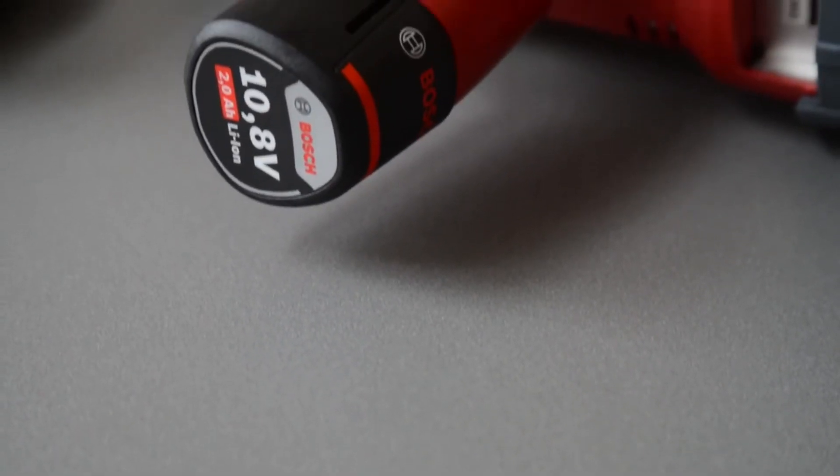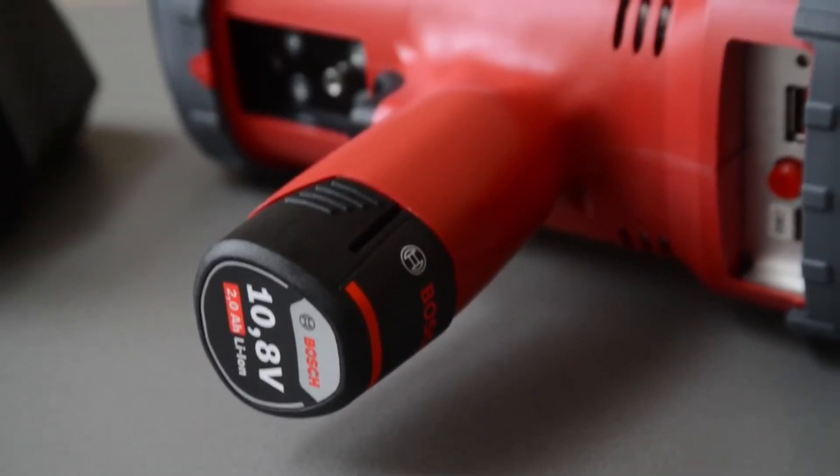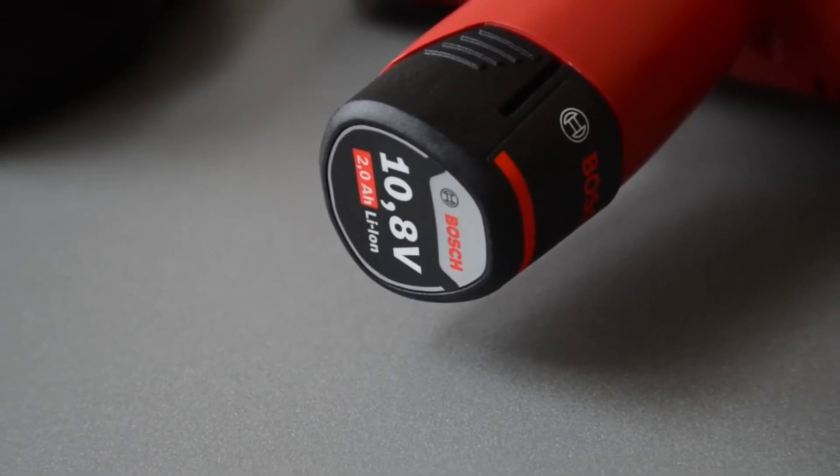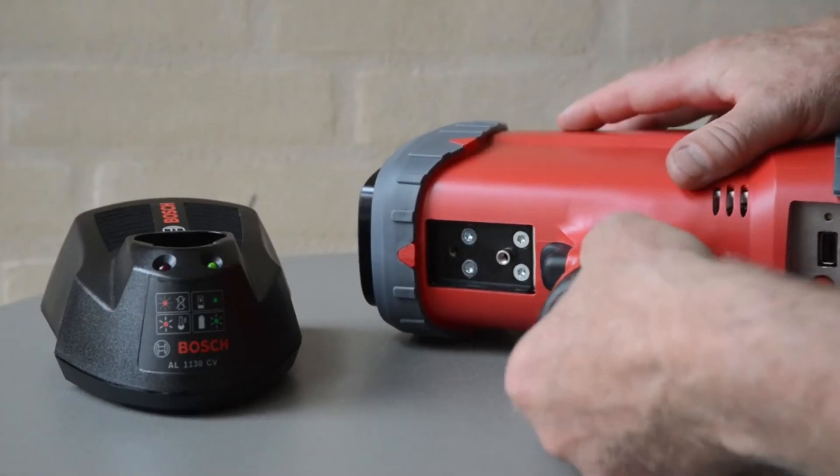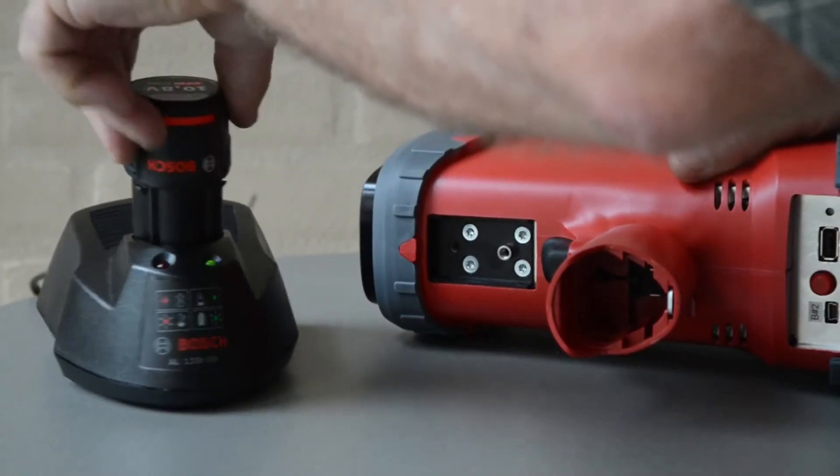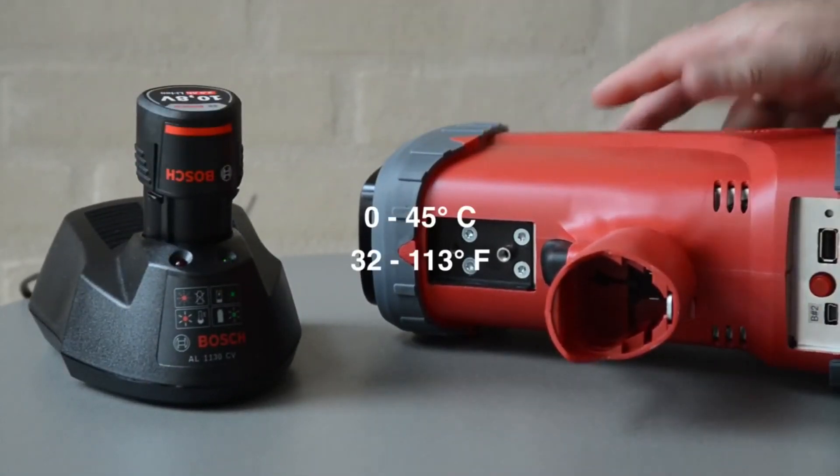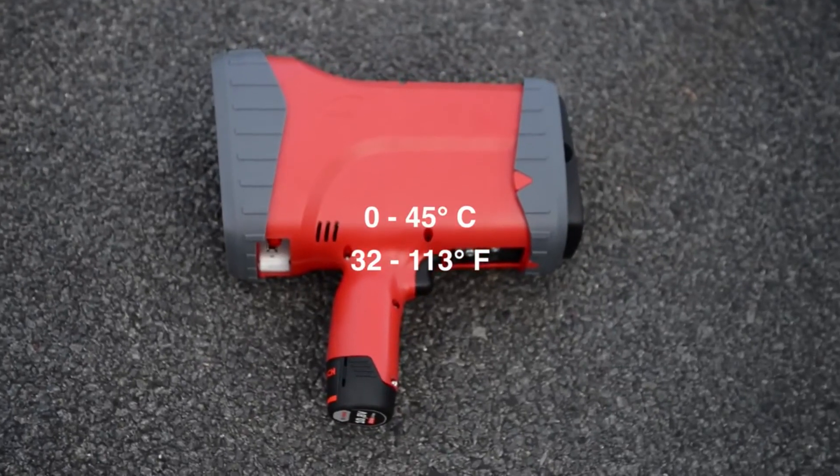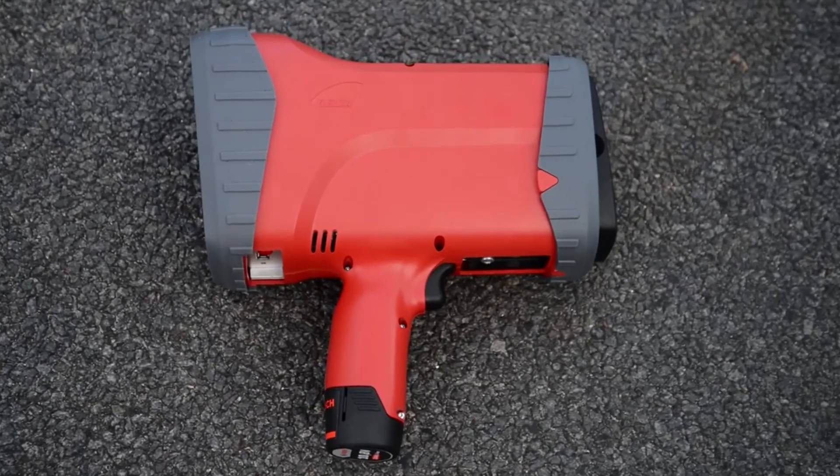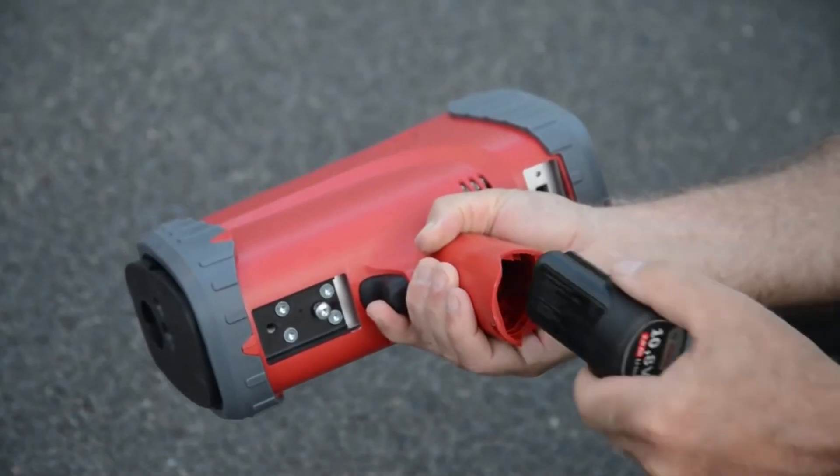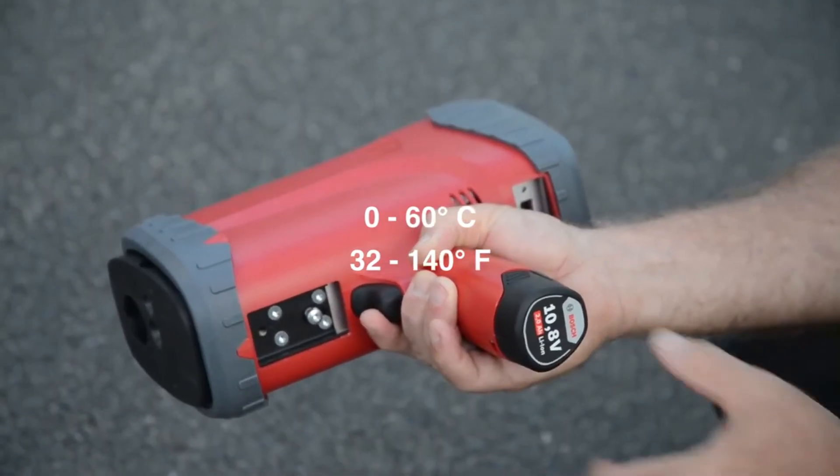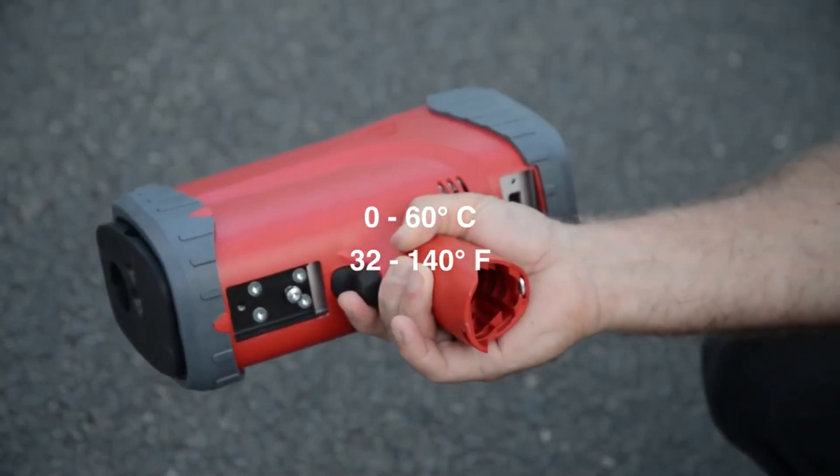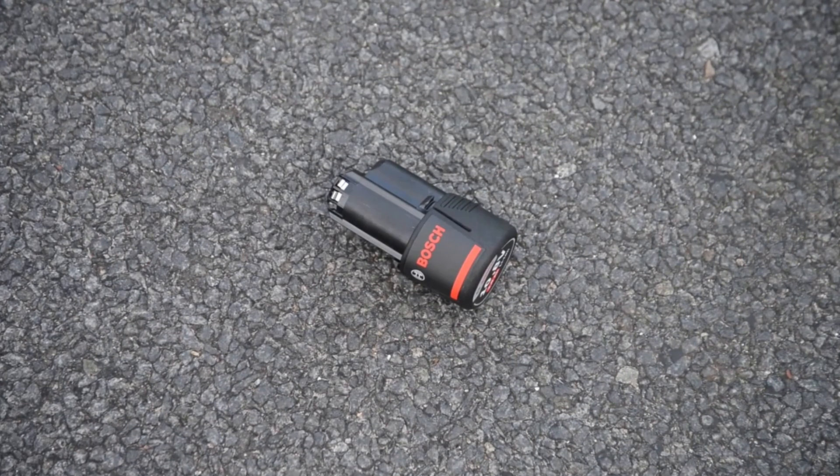The instrument is powered by a standard Bosch battery, which under normal use requires no maintenance. The battery is equipped with a thermal sensor that only allows charging within a range between 0 and 45 degrees Celsius or 32 to 113 degrees Fahrenheit. The operating range of the battery is 0 to 60 degrees Celsius or 32 to 140 degrees Fahrenheit. The battery will be fully charged in approximately 45 minutes.